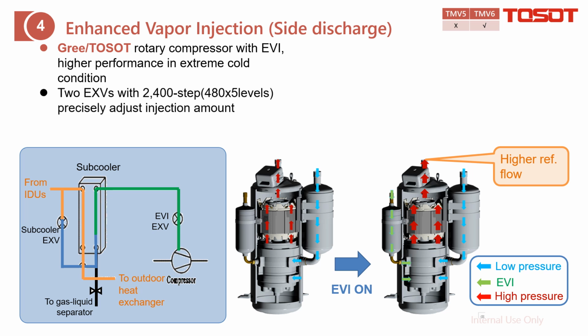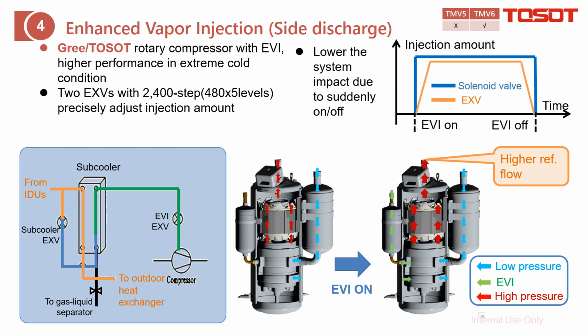And from this diagram, you can also find that there are two EXV for the EVI. Two EXV come together, we can have 2,400 steps. And instead of the solenoid valve to control the injection amount, we applied EXV. The reason is that with the EXV we can avoid the impact to the system due to the sudden on and off of the solenoid valve, which can ensure the reliability.